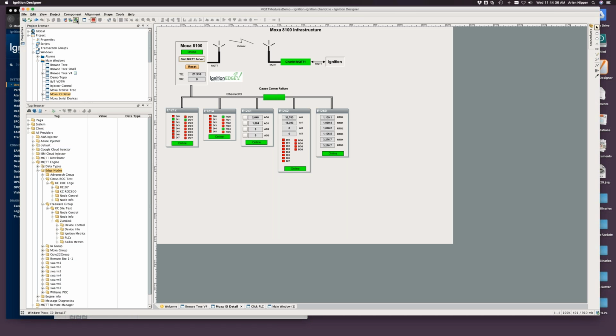So if I get into command mode here, we discovered all this information automatically, came up, and now we can pick a digital output, and we've got the digital inputs wired back to the digital outputs. So we can publish a command, turn on that digital output, scan it using the Modbus driver that's already in Ignition Edge, and now we're able to get that information back very quickly.